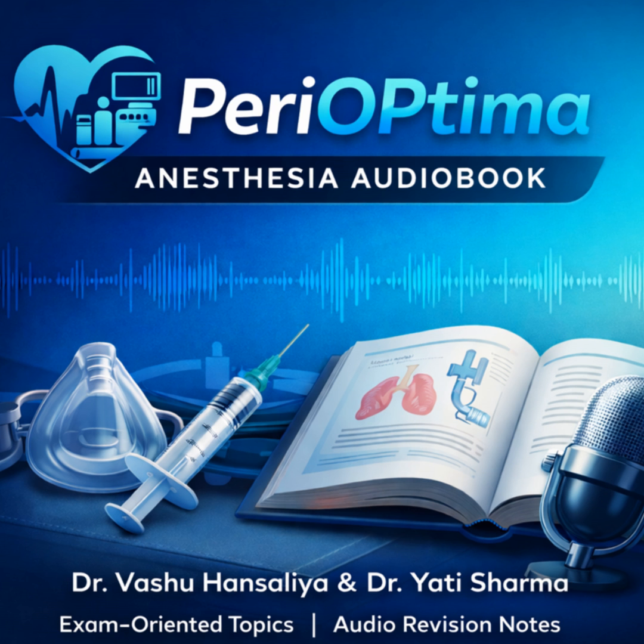So the knobs we turn on the front of the machine, they're the boundary line. Exactly. The flow control valves, the knobs for oxygen, nitrous, air, they are the gateway. Everything upstream of those knobs is intermediate pressure. And everything downstream is? The low-pressure system. Let's talk about that low-pressure system. Why is this distinction, this three-part model, so critical for an anesthetist to understand?